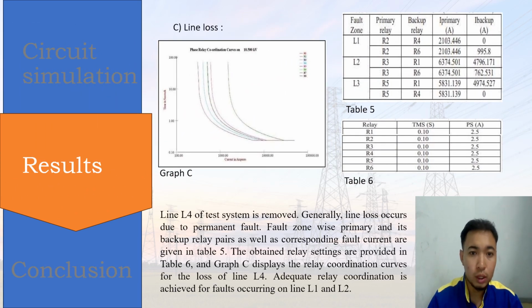Next, for the third part of the result, which is line loss. Line 4 of the test system is removed. Generally, line loss occurs due to a permanent fault. The zone-wise primary and backup relay pairs, as well as the corresponding fault current, are given in table 5. The obtained relay settings are provided in table 6, and graph C displays the relay coordination curve for the loss of line L4. Adequate relay coordination is achieved for faults occurring on line L1 and line L2.